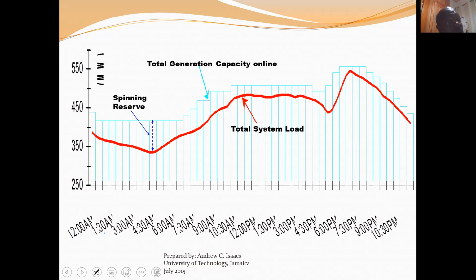The fact is, even though the generators just trip, apart from the fact that they need to bring them back on in a particular sequence—because if you just turn them back on with the same load on the system, you might trip them again—so we do have generation sequencing to consider. But especially your steam units, once they have tripped offline, you can't just bring them back online immediately.